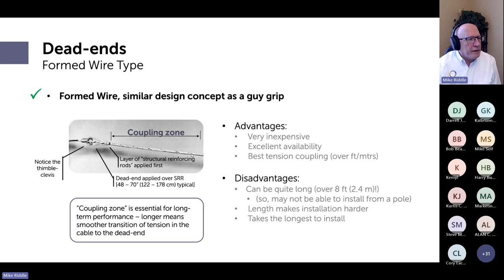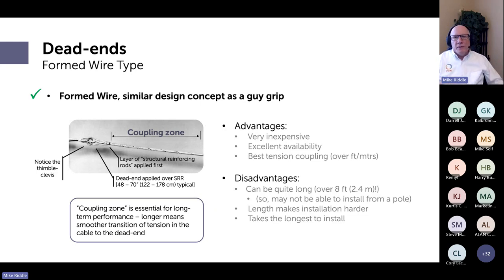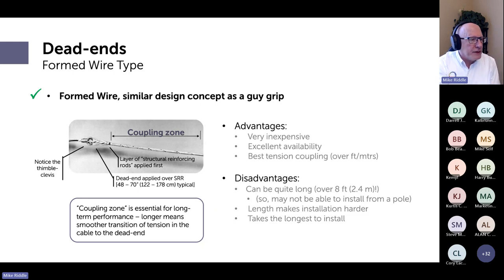This is a good point to introduce the concept of the coupling zone. Fundamentally, you have to get the tension in the cable coupled to the dead end, which is then connected to your structure. The distance over which the tension transitions from the cable to the dead end is called the coupling zone. You want it to be as long as possible, but in the real world you balance coupling zone length against ease of installation and practicality.